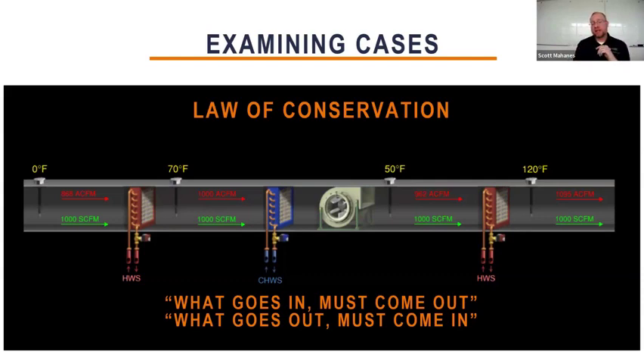And so what's interesting is I cannot measure volume on this side and allocate that measurement anywhere else where there's a density change. And believe me, I've done this hundreds of times in my career. It took me 2 weeks of lamenting when I realized I was actually incorrectly allocating the CFM value. And it's not that I'm measuring volume incorrectly. It's that I allocate it incorrectly. And so that's one of the strange things about mass flow, that if you see it from that perspective, you can actually understand what's really happening.